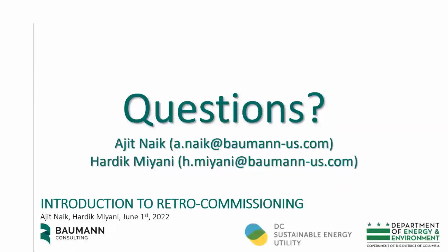There was a question earlier that I don't know that we answered about life cycle determination. I'll give my answer to that. We look at typical life cycles from ASHRAE. There's an ASHRAE guide or standard that talks about typical life cycles, and we look at existing life, and we'll also do some evaluation of equipment condition when we're projecting out life expectancy for equipment. We might also look at things like type of refrigerant. If it's using a refrigerant that's phased out or phasing out, we would assume that equipment is going to need to be replaced sooner rather than later. But it's an engineering judgment on that one.